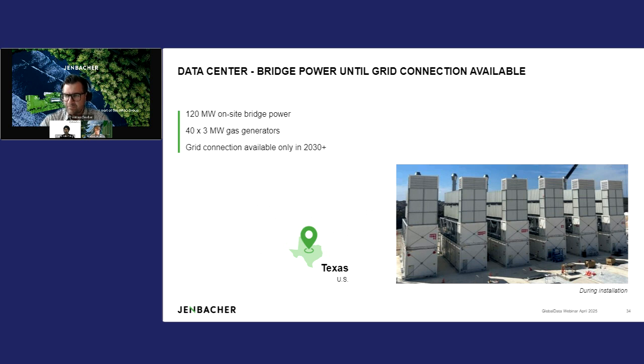This can also be integrated into a microgrid. In addition, what's very interesting is that due to our favorable start time and excellent load change behavior, we normally do not need to add any battery storage systems. So we can handle that without them, even for heavily changing loads if you move into AI applications. The catalyst is also integrated. Everything is emission compliant to be able to run 24/7, 8,760 hours per year.